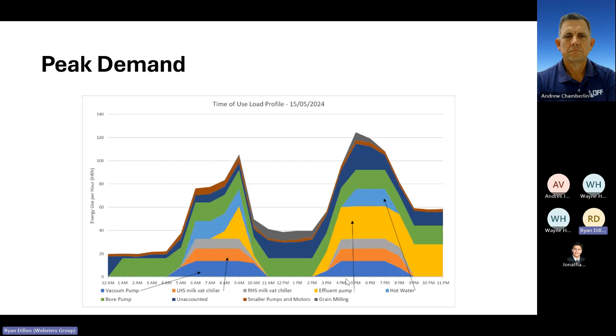So this time of use balance in an audit helps not only identify the bulk efficiency, but also time of use efficiency, which is really key. And using that analogy of the profit and loss statement of the cost of every motor, we're looking at putting in Fluke 1738 power loggers that have amps, volts, power factor associated with every motor. So in that profit and loss, energy accounting, developing a balance sheet for what your liabilities are from an energy cost perspective, we find the outliers.